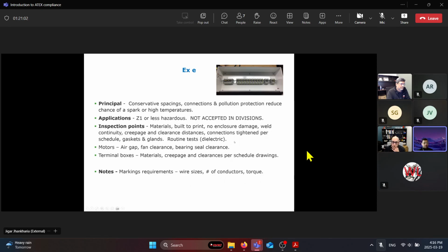Inspection points. This was something that Ray, in your email, you had said, what is something that we can look at during our design process. So these are some of the items that you can look at: material usage, built to print, enclosure damages, any weld continuity, any creepage or clearance distances. Again, these are stated in the standards. Any connectors, connections tightened per schedule, gaskets and glands, and routine tests on your product. So those are some of the key things to keep in mind for this method of protection itself.